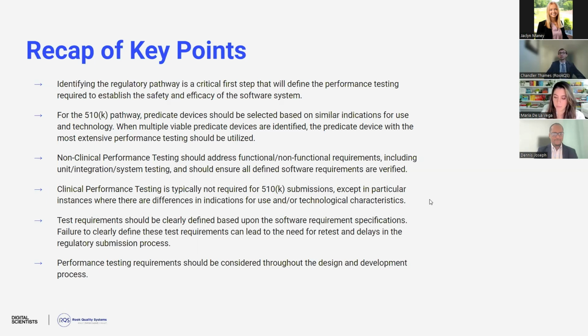For clinical performance testing, it's typically not required for 510(k) submissions, except in particular instances where there might be differences or gaps in the indications for use, technological characteristics, or again, if there have been any recalls or adverse events that are of significant concern to FDA for the predicate device.